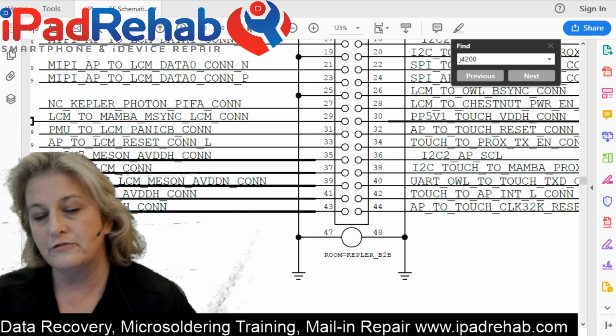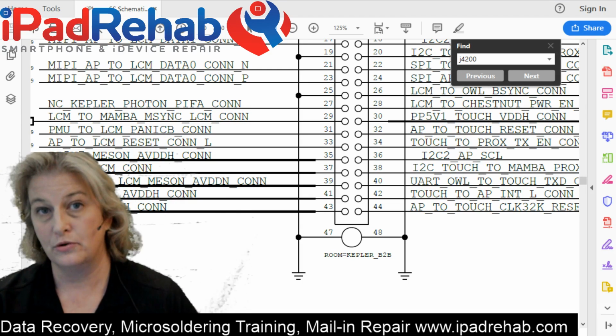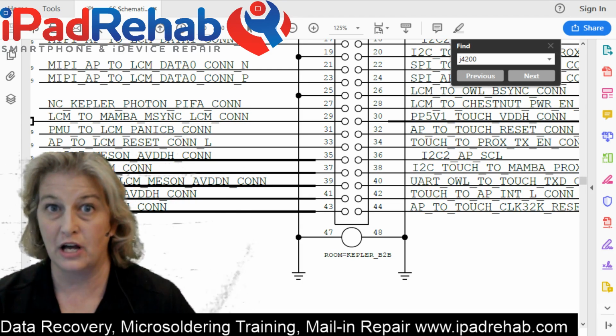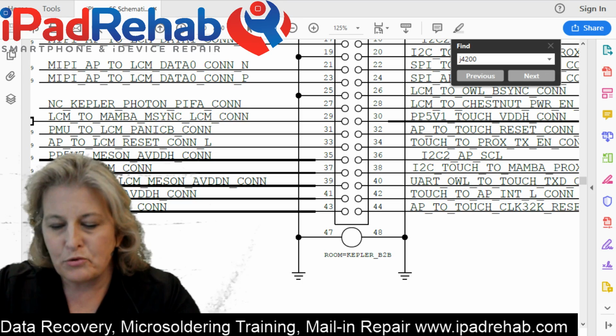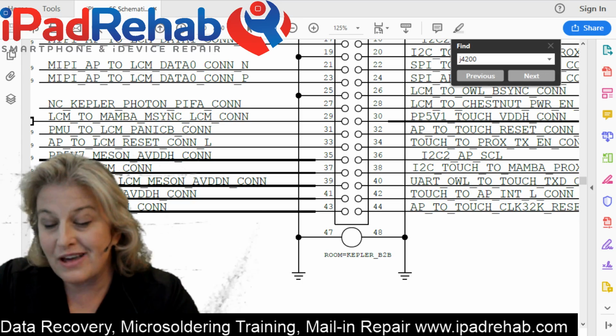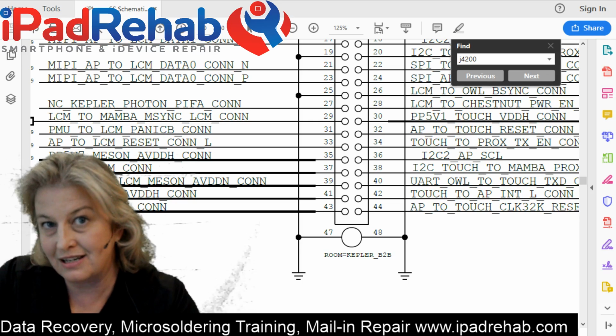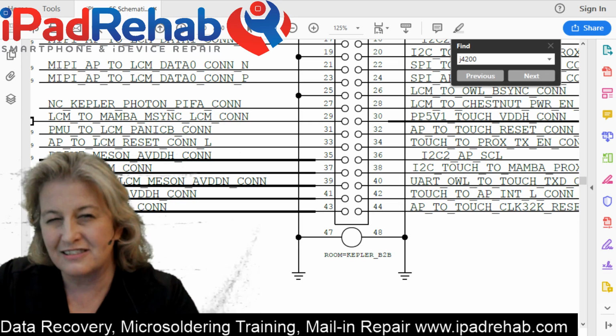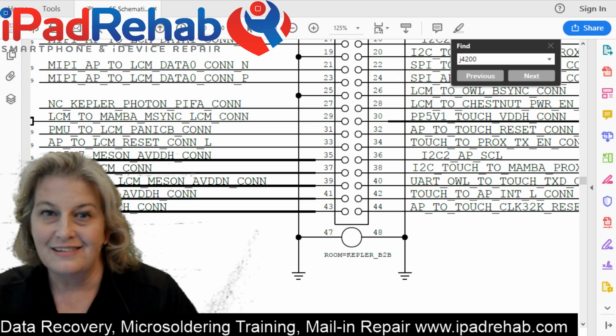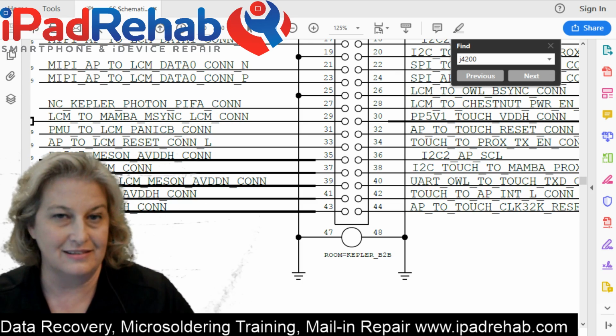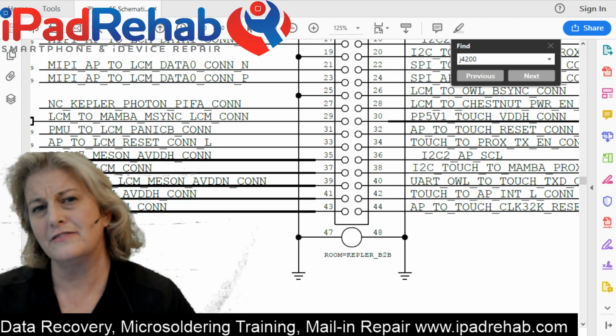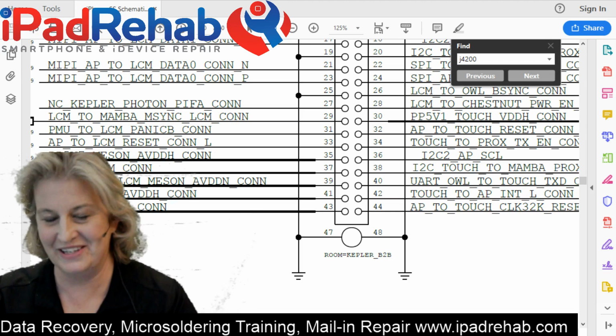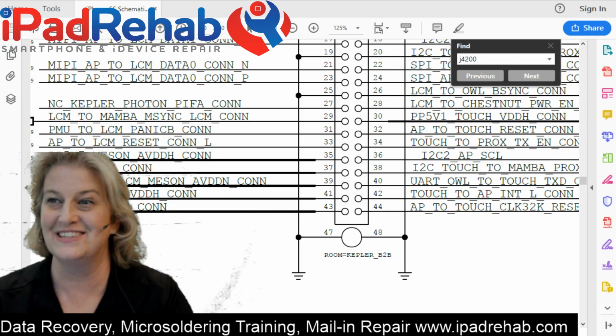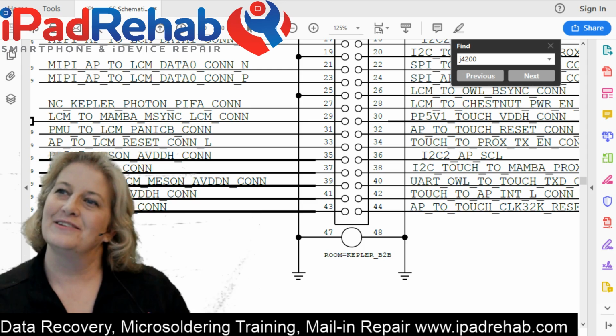So if we wanted to do a voltage test, we would have to have this thing booted up under power with a screen plugged in, and then we would have to get our probes in there, now it's under power, without touching ground and actually take a voltage reading. That's tough to do. So it would be nice if we could do a voltage test quick and easy, but we can't because of clearance, and there's no place to stick a probe if you've got a screen on there. So what else can we do?